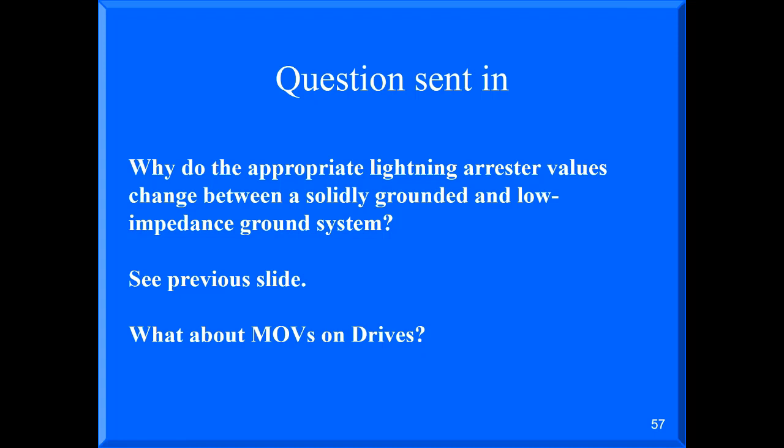And it ranges. We talked about sizing: on the 480 volt drives, manufacturers say they're 1500 to 3000 volts. When we're testing, we've actually seen them withstand 10,000 volts through capacitor discharge testing, simulating lightning strikes. And with a surge protector, we were able to withstand 20,000 volts.